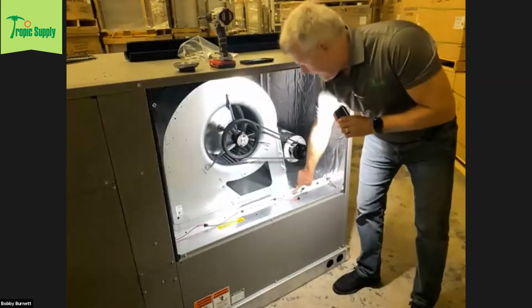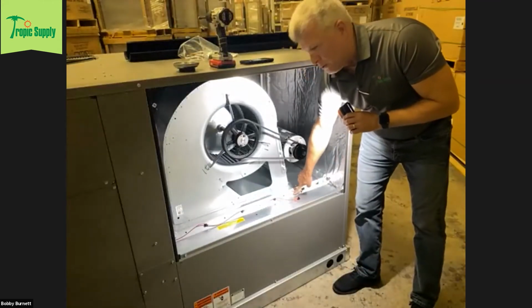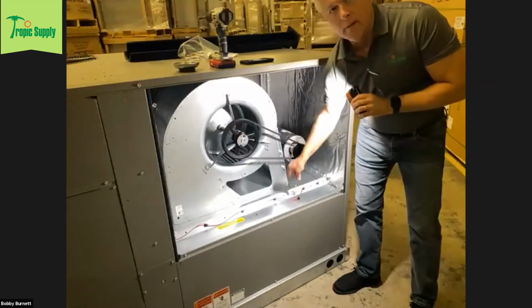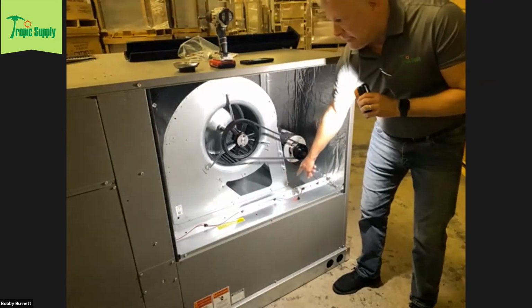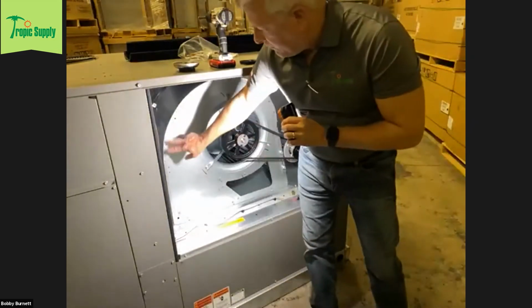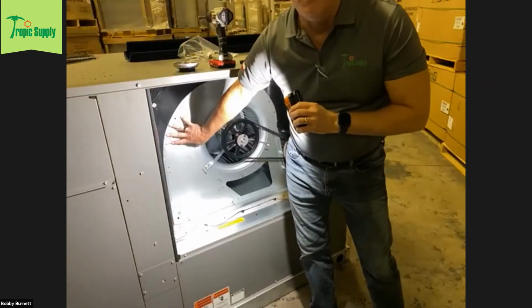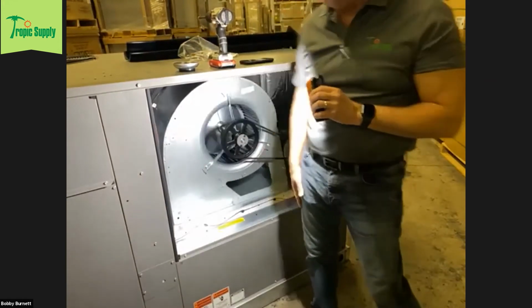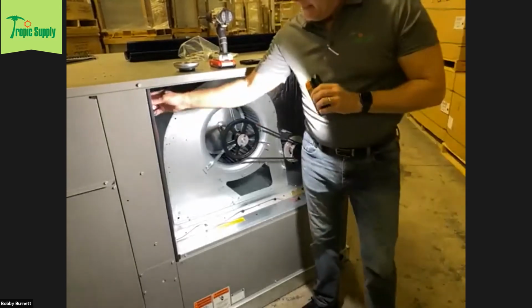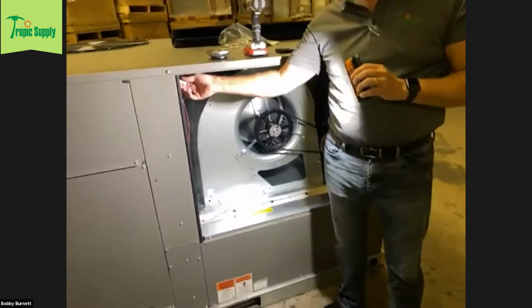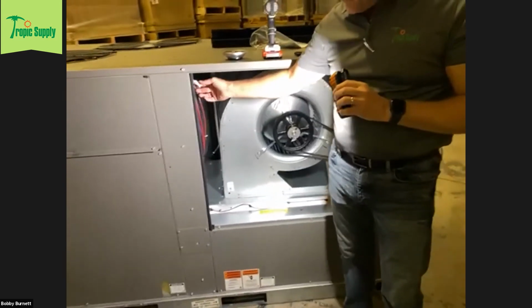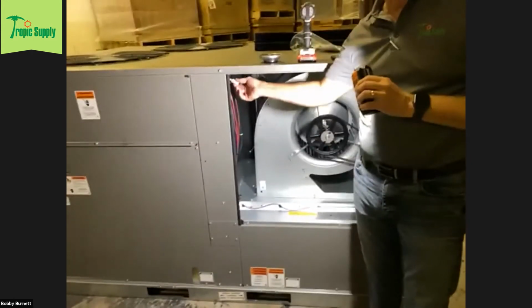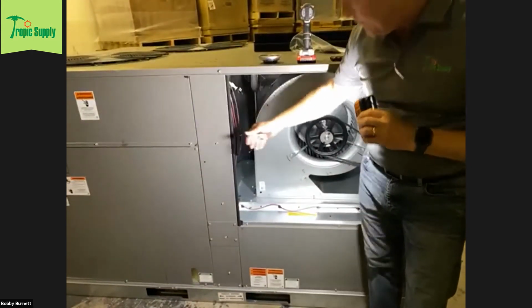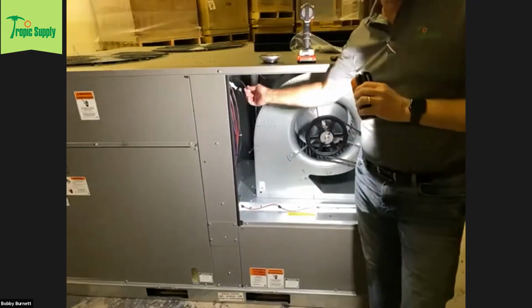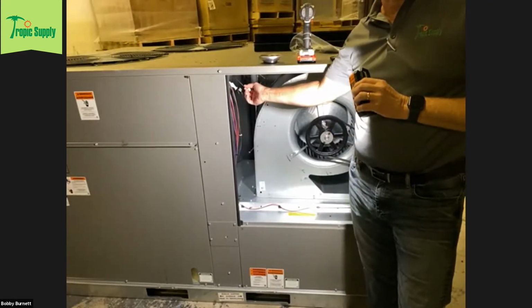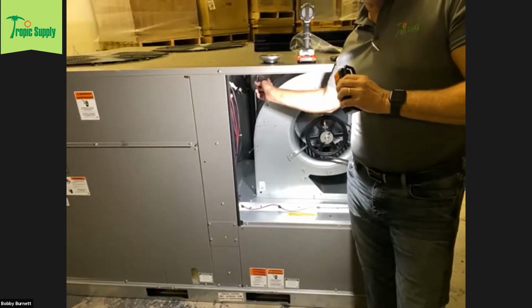You also have an access port here where you can screw in a sampling tube for a smoke detector. There are mounting holes over here where the factory would mount a smoke detector if you order one factory-installed. Up in here there are a couple of plugs: this one attaches the smoke detector to the circuit control board, and this other one is for an enthalpy sensor if you're using the economizer.